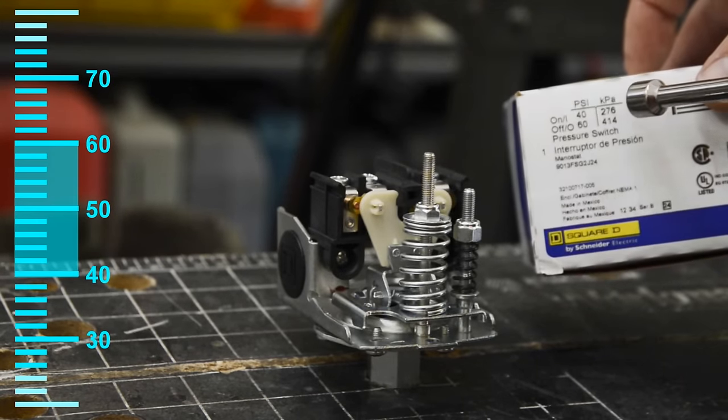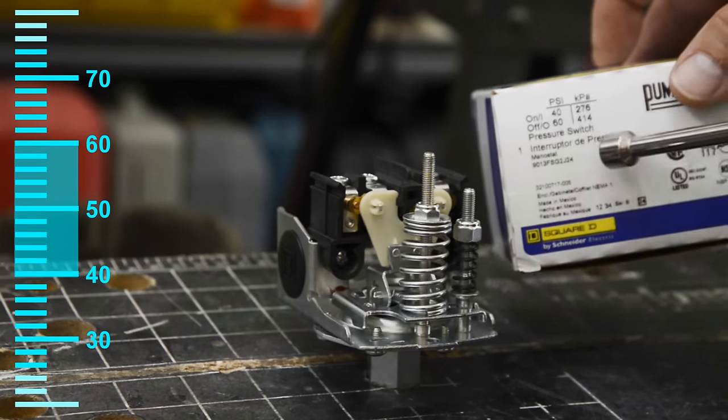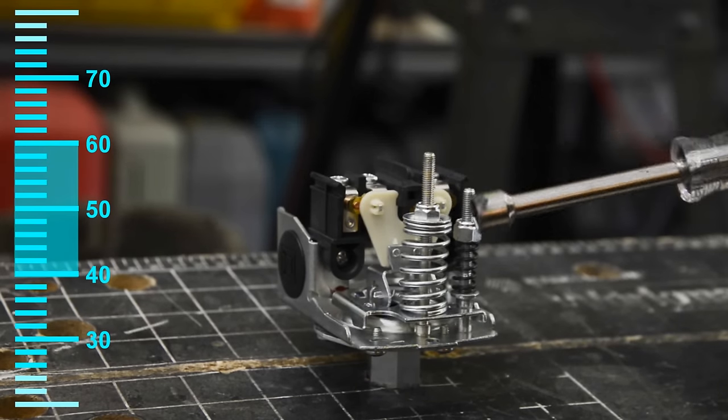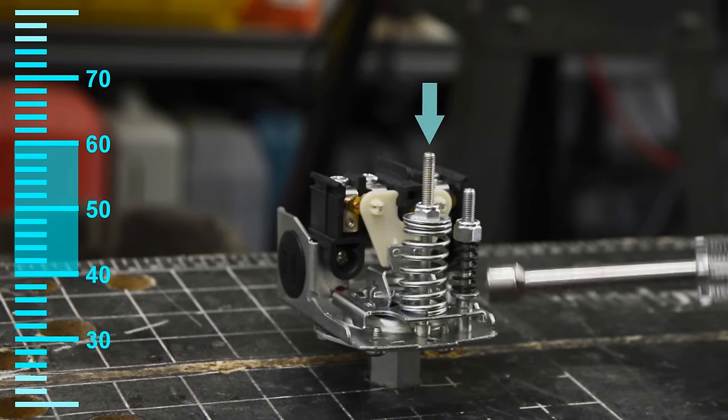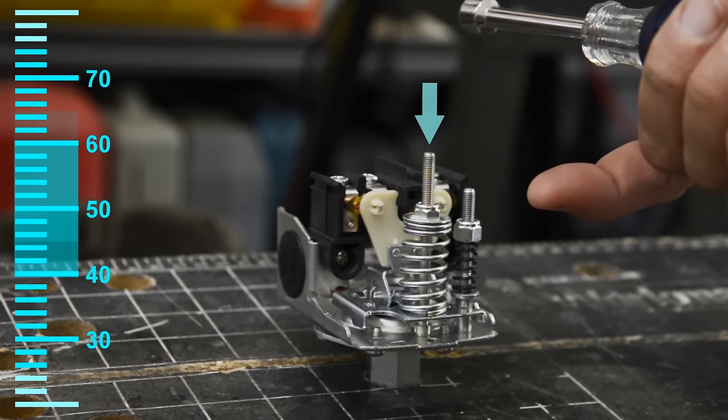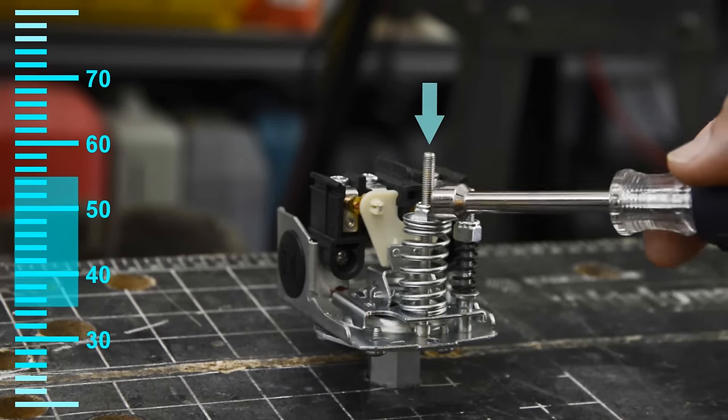There's also 30/50s that are used for household well pumps, but for commercial applications that require a little more pressure, it's more often that you're going to see a 40/60. The center adjustment does that range from 40 to 60, and you can raise the range to 45-65, or lower it down to 35-55 with this center adjustment.